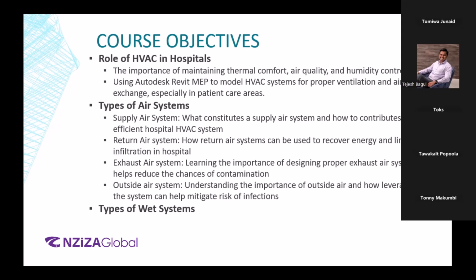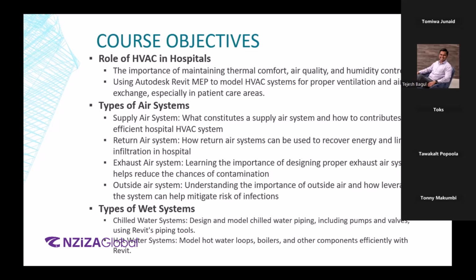They are sometimes also called water systems, but since we are using a lot of direct expansion, VRF technology, it's starting to be called wet systems rather than just water systems. That is why I mentioned this as wet systems. In the wet systems, of course, we will talk about the chilled water systems for cooling the areas. We'll also talk about the heating hot water for making sure that the temperatures are maintained in the area, which is getting too cold, right?